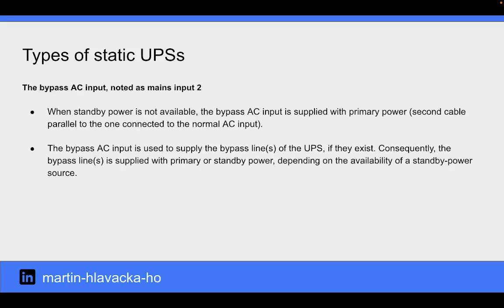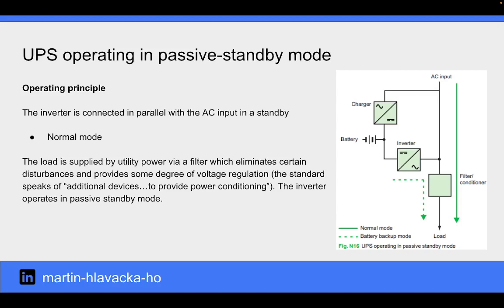A UPS operating in passive standby mode has the inverter connected in parallel with the AC input in a standby configuration. In normal mode, the load is supplied by utility power via a filter that eliminates certain disturbances and provides some degree of voltage regulation. The inverter operates in passive standby mode.